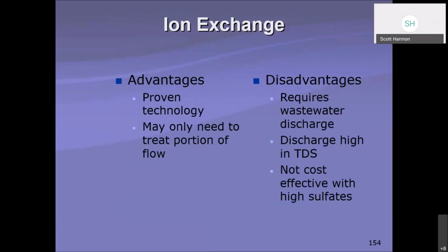Disadvantages: requires wastewater discharge, and that sometimes is not easy to do. Discharge is high in total dissolved solids. Again, your wastewater folks may not like that. Not cost effective with high sulfates, again, because those sulfates combine with the brine and use up the brine's effectiveness before it even gets to the arsenic.